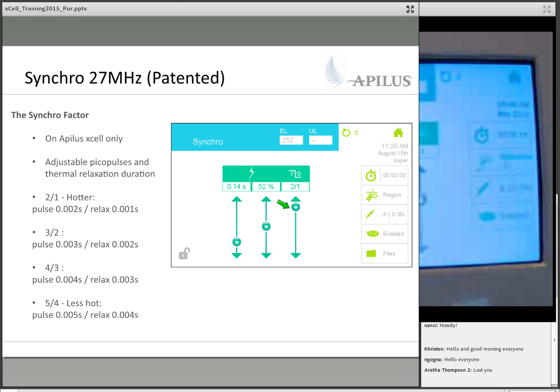Keep in mind that the most important of the two numbers tends to be the thermal relaxation—how much time you leave for the heat to dissipate out of the tissues determines if the pulse is hotter or milder. So 2-1 is a 2 millisecond pulse with a 1 millisecond thermal relaxation. There are a lot more combinations now.